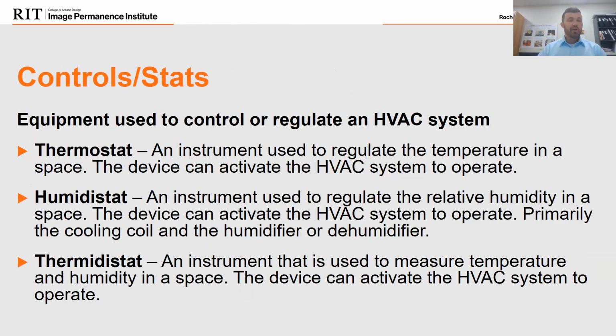So also there's our controls or stats. This is the equipment to regulate the HVAC system. Your thermostat, which I'm assuming most, if not all of you have within a space, is what's going to regulate the temperature. It's going to decide: do I heat, do I cool? It's controlled by your thermostat. There's also humidistats. A humidistat is the instrument that regulates the relative humidity. This tells your HVAC system, am I dehumidifying? Am I humidifying? Am I adding moisture to the air as it passes?